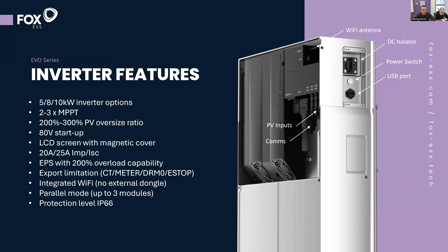So this is just looking at the battery then. Integrated into this unit is a 10.24 kilowatt hour LFP battery. This will provide a high charge rate, so if you had the 10 kilowatt inverter model of the Evo - give or take, because the charge power is subject to certain variables like temperature and SOC - but all things being equal, it will charge at the full rate of 10 kilowatts. So what you're getting here is essentially 1C charging, meaning the battery in just over an hour will fully charge. In that example, with a 10 kilowatt charger, it's 95% DoD on this. Historically our products have been 90%, but this allows you to use 95% of the rated capacity.